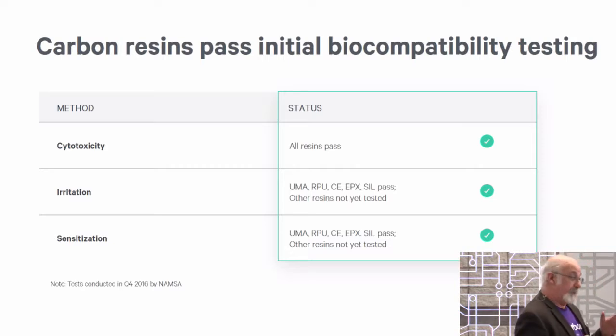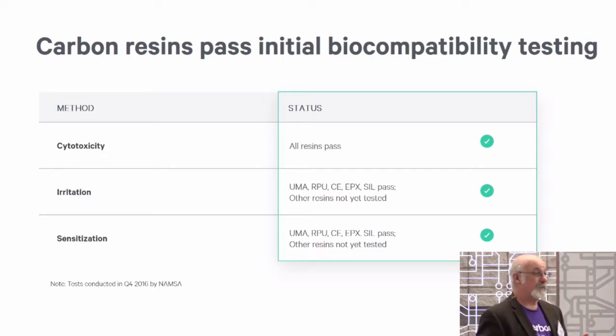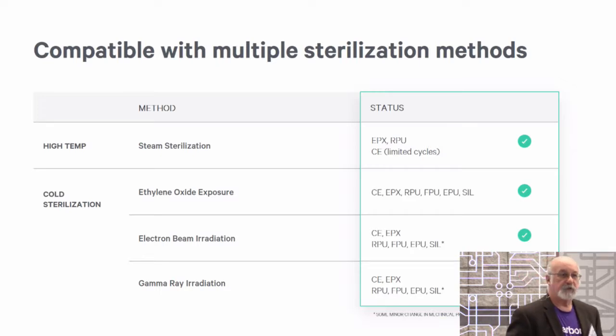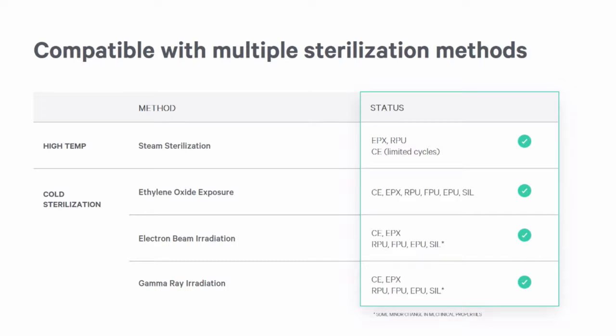If biocompatibility was the only benchmark, then we'd be fine, but the reality is when you bring an object into the OR, it has to be sterile, which means that besides being biocompatible, you have to survive sterilization conditions. So we've challenged all of our materials with all of the normal modalities for sterilization. So high temperature sterilization, our EPX material, and our RPU material, which is surprising. It's a lower Tg material, but it's a thermoset. So it survives and maintains its geometry under steam sterilization for as much as 300 cycles of sterilization.